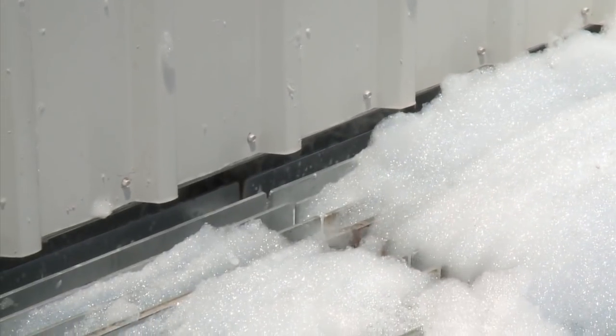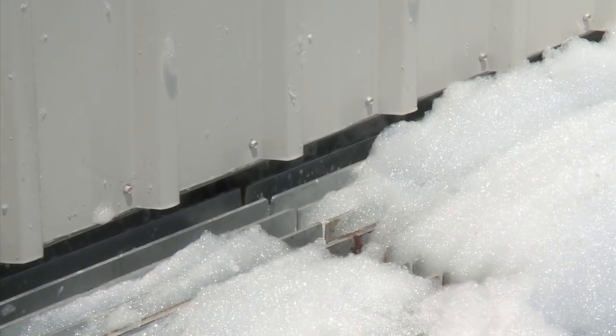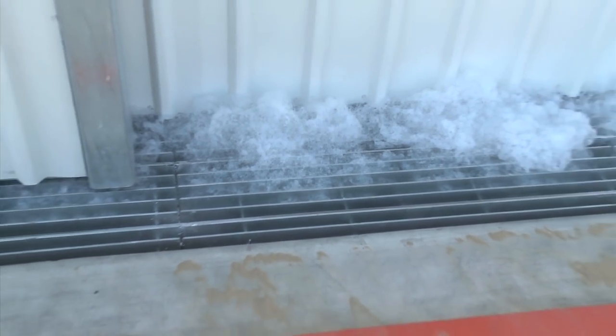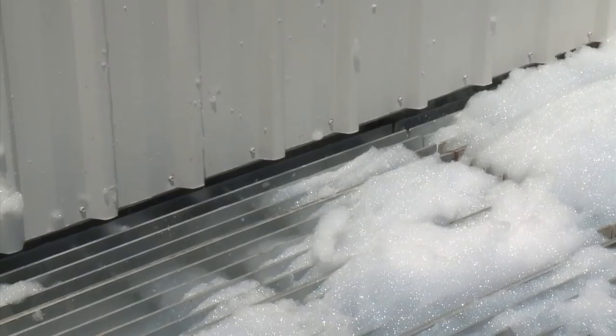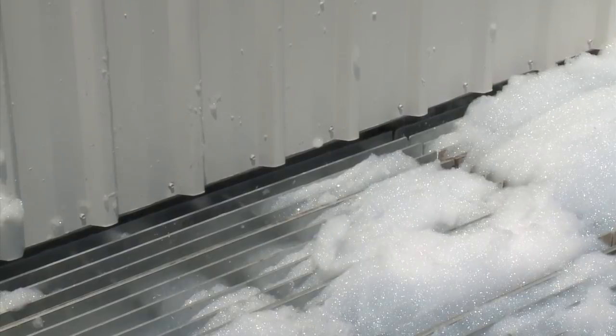firefighting foam and aircraft wash down. This meant incorporating a spill capture system into the design solution. Normally a traditional hangar foam system would require a capture tank with a capacity of over 500 cubic metres, due to the high volume of foam that these systems discharge.